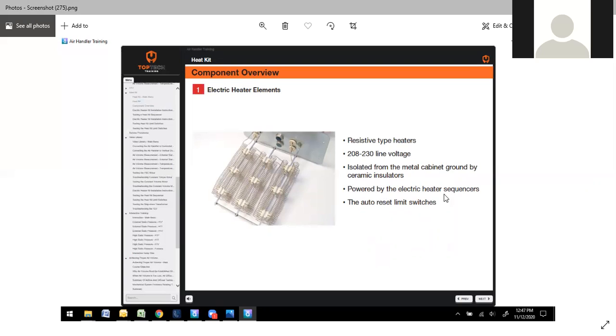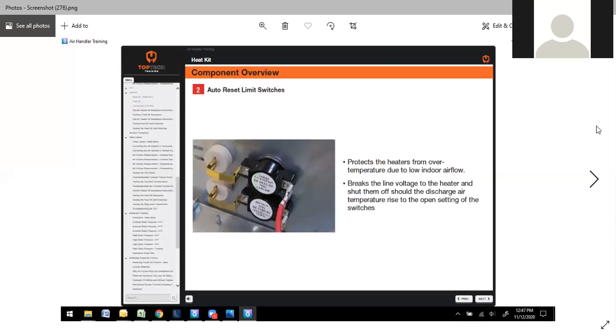Powered by the electric heater sequencers. They do have auto reset safety limits. They will reset many times, but eventually they will open up. The safety limits protect the heaters from over temperature due to low airflow.